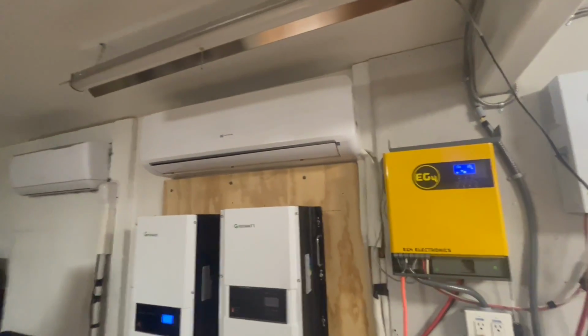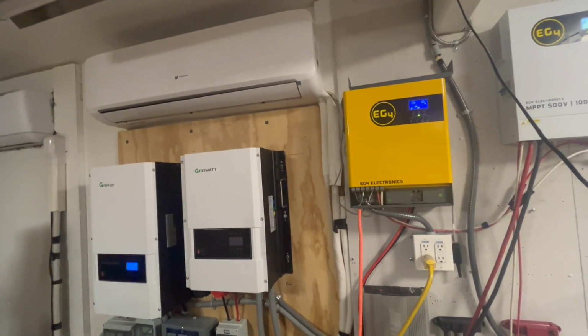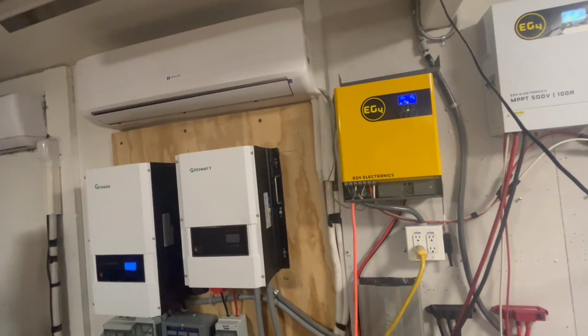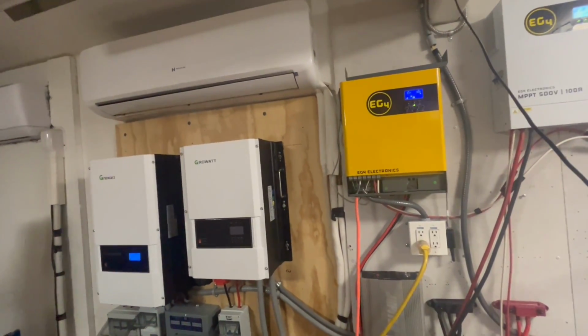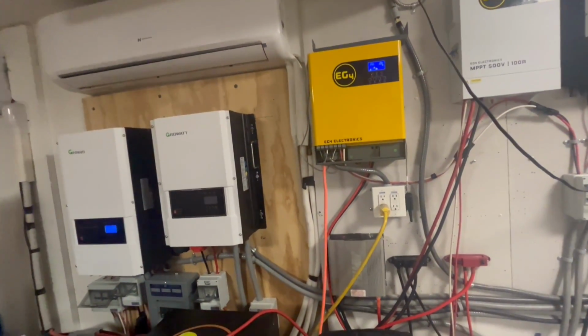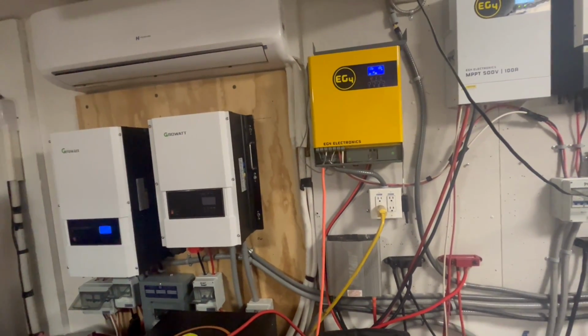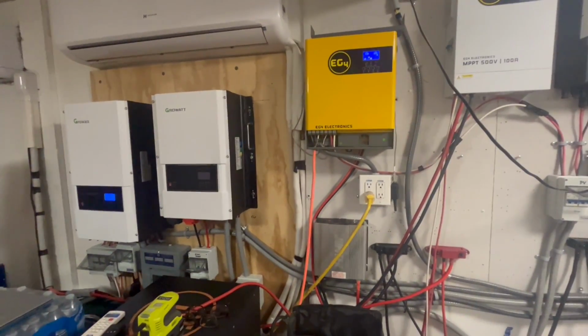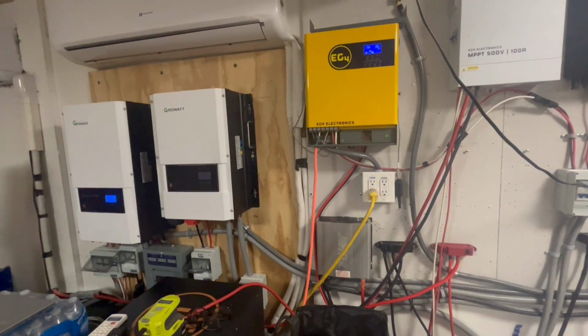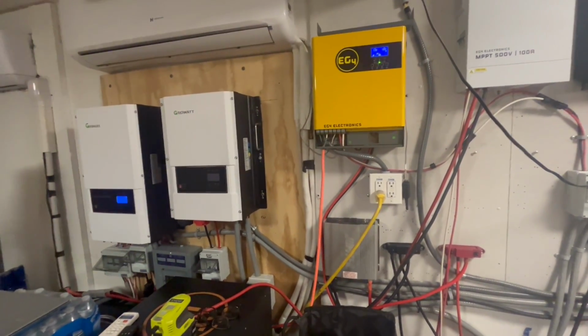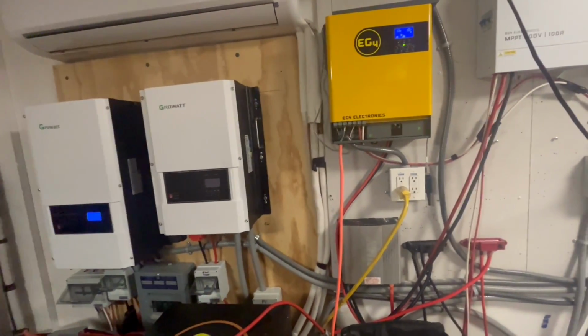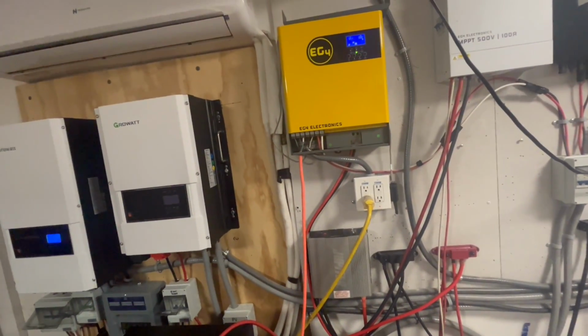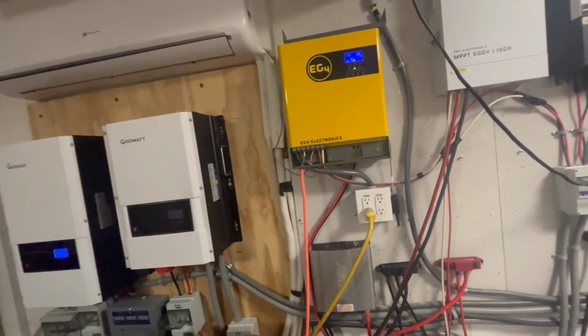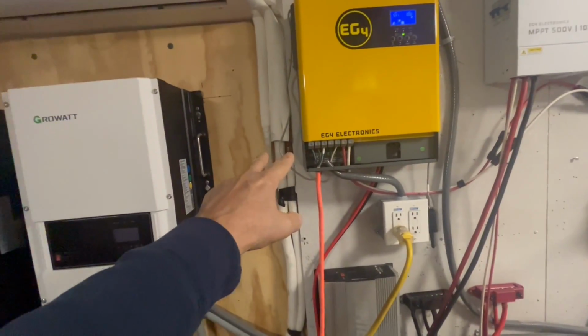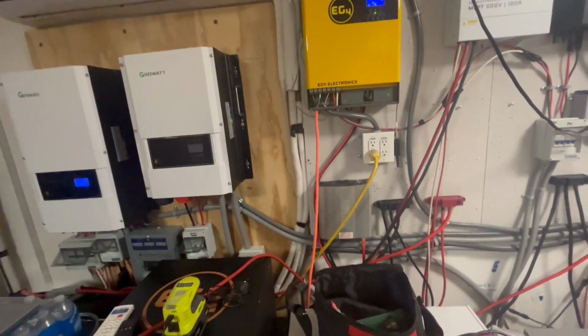What that Nylog Blue does is it seals those threads, and with the amount of lower pressure you have on this compared to a regular heat pump or air conditioner on your house, it's thick enough. It's almost like honey when it comes out, real sticky and thick, and it keeps the refrigerant from getting through the threads and leaking out on you. It covers the threads where you connect here and outside, so I really highly suggest it.